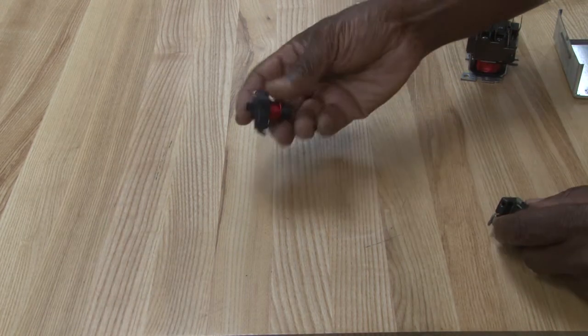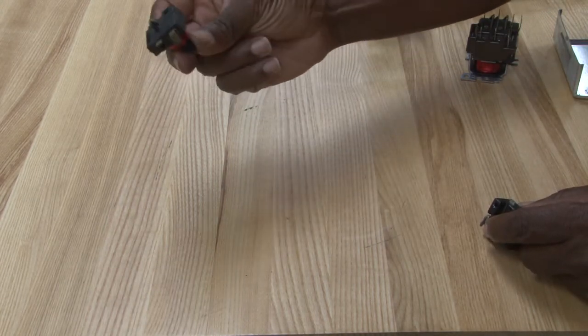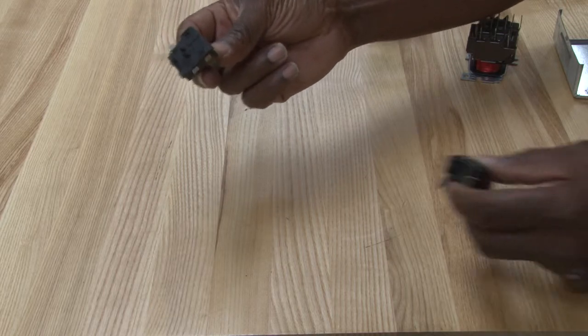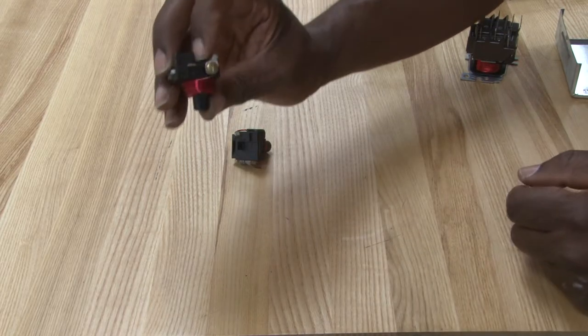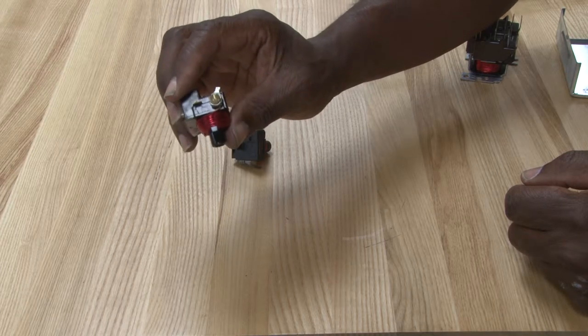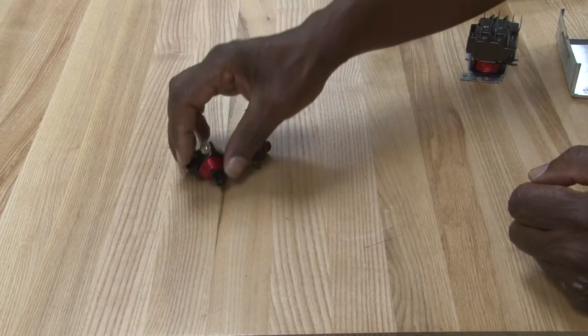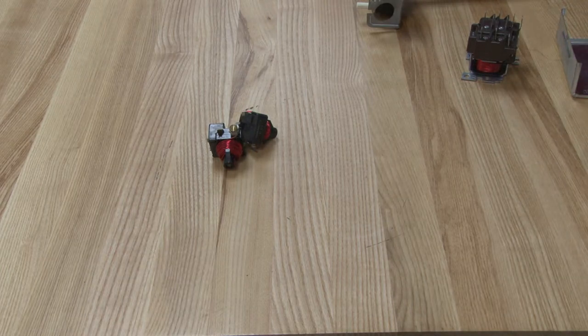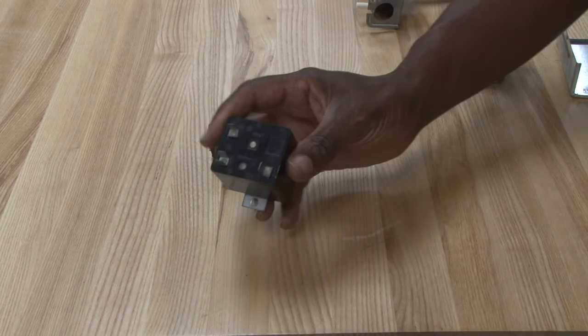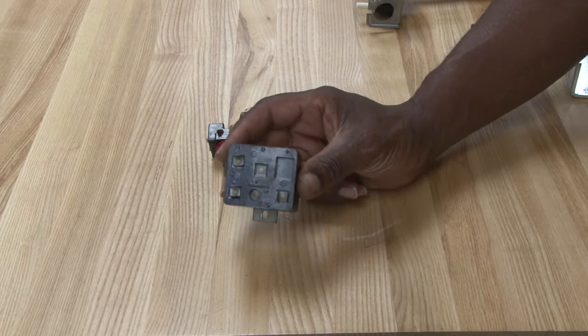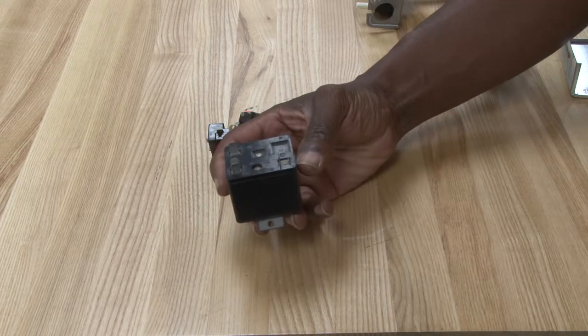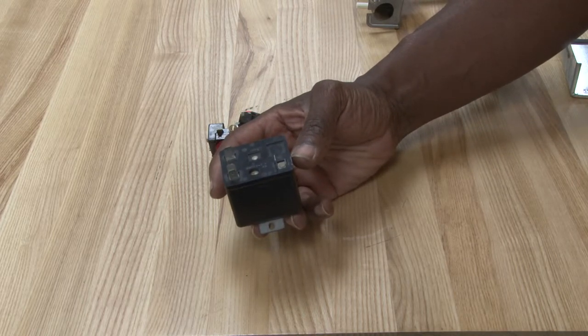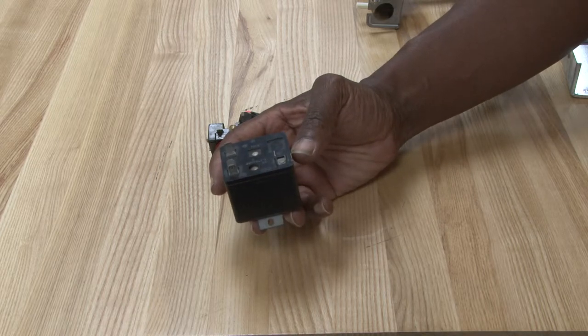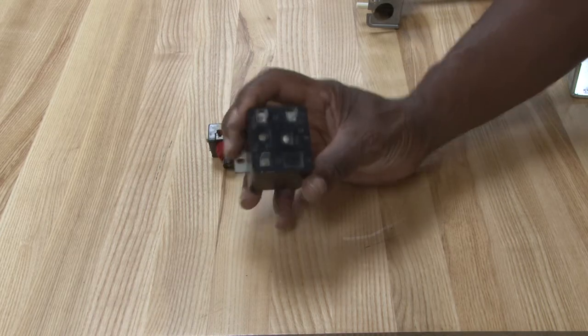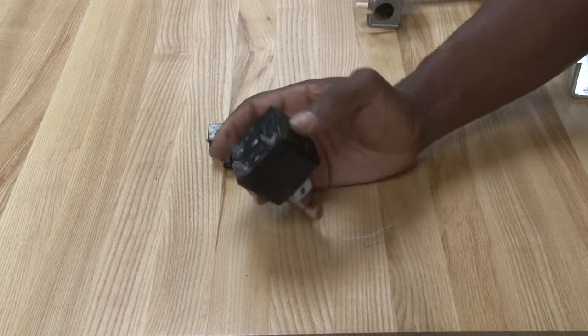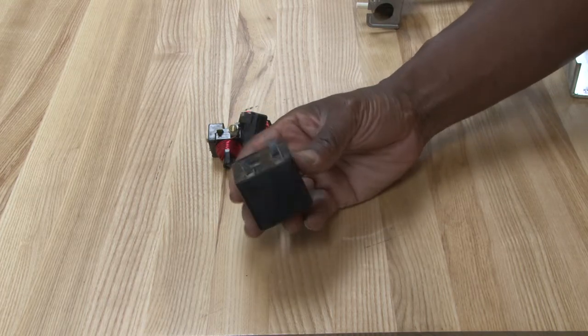Other types of relays we may find, like for compressors, little small hermetic compressors, will have this type of relay used to take out the start winding. That's another type we find in the field, which is called a potential relay. And that's for larger compressors. It has three terminals on it, and it has a special coil that senses the inductance from the start winding. And this device here is used to take out the start winding also.